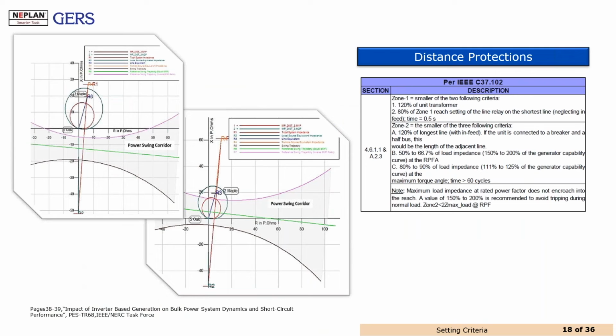Another selective protection is the distance protection. I am showing here some examples or criteria according to the standard for generator protection. This protection is different from the overcurrent protection because it is based on the impedance graph. Depending on the behavior of the load and of the fault once we have any event, the relay is able to send a trip signal depending on the operation zone. I mean, whether we have zone 1, zone 2, or zone 3, and it depends on the fault location on the system.